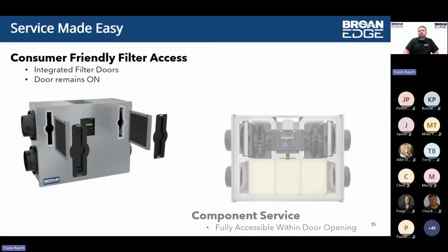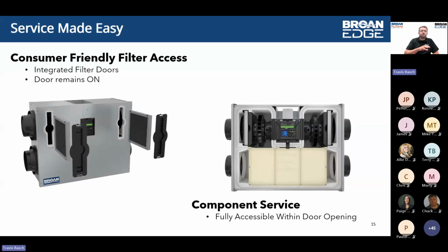Jump forward here back to where we left off. So again, service made easy. You can see the access doors there. Again, consumer friendly, as well as, if and when we've got to get to those key components for service, you do have the ability to do so by removing that door completely. Do note with this type of design and how we're using the insulation, basically that foam shell, we are able to upgrade the service interval for the recovery core. Instead of that typical 1 year service of a recovery core like we have with a multitude of our other products, as well as other products out in the industry, because of this design and how we're going about the recovery core design, we will now go to a 3-year service requirement for that recovery core.